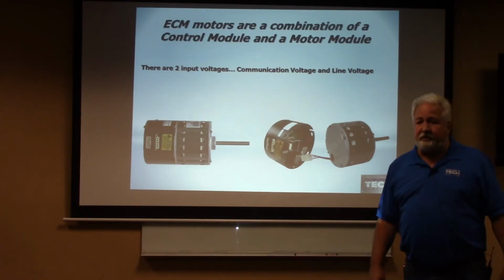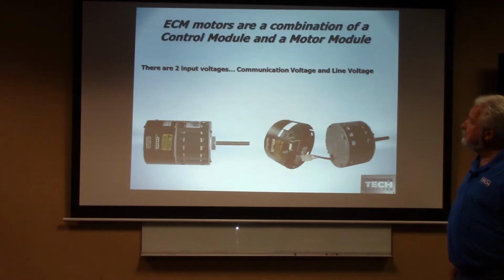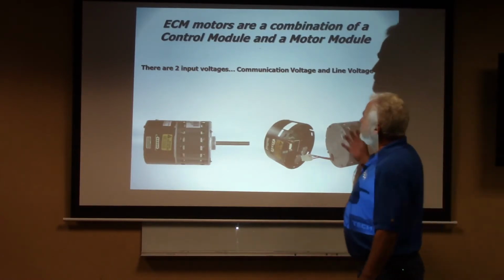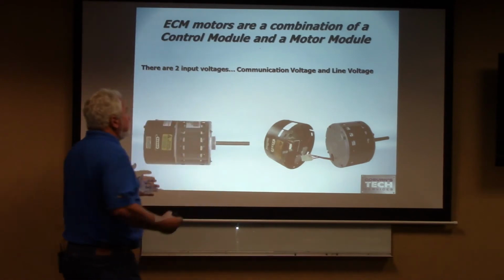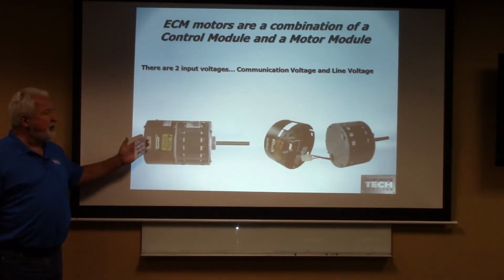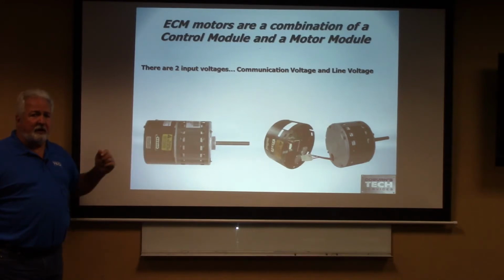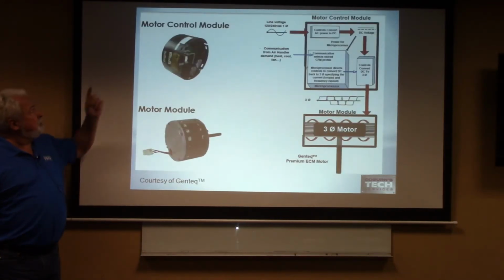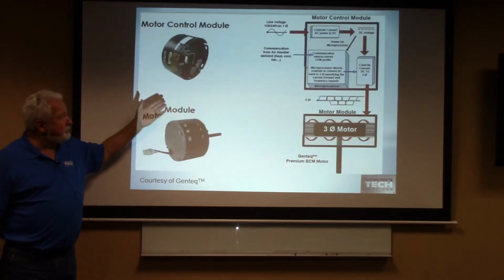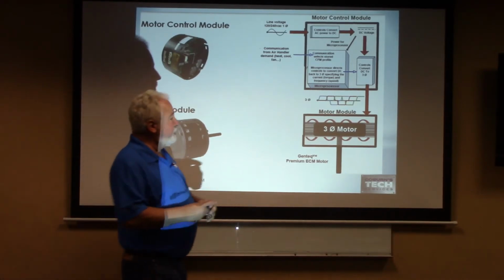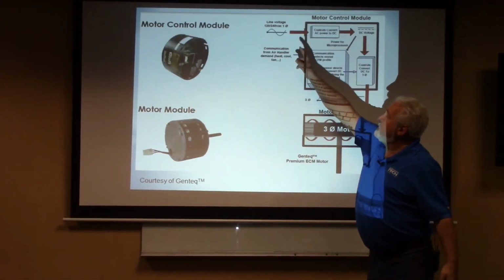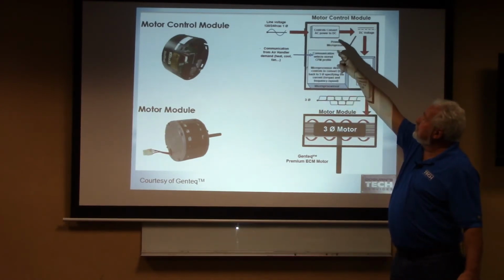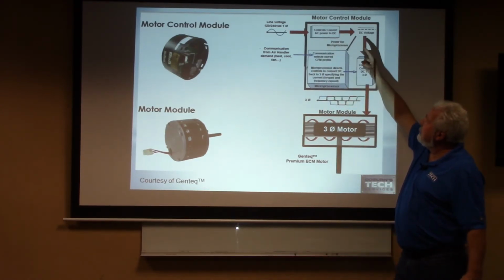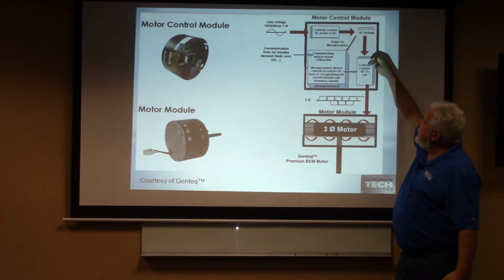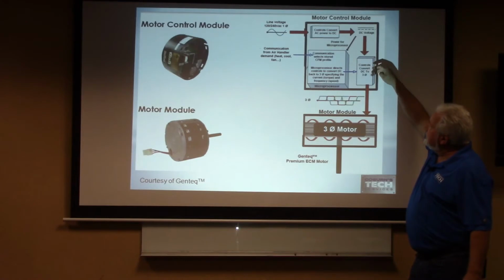So let's take away some of the magic on some of these things so that you guys get it. ECM motors are a combination of a control module and the motor itself. There's two inputs: you'll have the communication voltage and the line voltage. That's basically it. The motor controller module and the motor module just open up and separate. There it is. I like this graphic because it really shows what happens. You take 120 or 240 volts in, it goes to a control, which converts that AC power to DC power. Once you convert that over, now we're going to convert that DC into a three-phase.